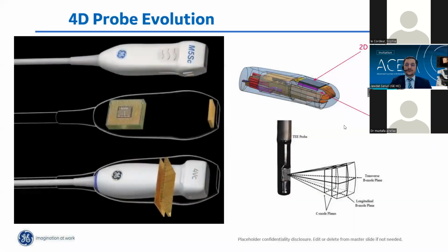And thanks to these microchip CPUs mounted right below the surface of the matrix probe, we can process this much data, having such 4D probes with such a high number of elements at the same size and even weight as the normal 2D probe and, most importantly, a cable of normal size. And this applies to transthoracic probes as well as transesophageal probes.